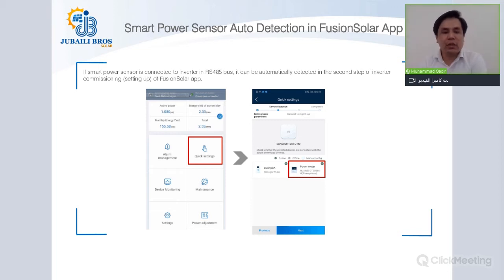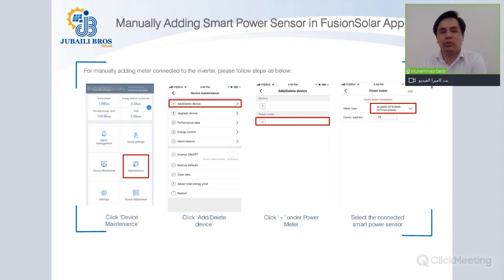The next scenario is that you have an option of manually adding the power meter. So how will you do that? Manually adding the smart power sensor is under the quick setting. You will find device maintenance. You will click that. The next step will lead you to the option of add/delete device. You will click that option, and then that will prompt you to the next window where you will have the option of adding power meter. So you will click that power meter, and that will lead you to the type of control that you want. So select the connected smart power sensor model, either a single phase or a three phase, with the right model from here, and then the communication address, usually kept as 11.